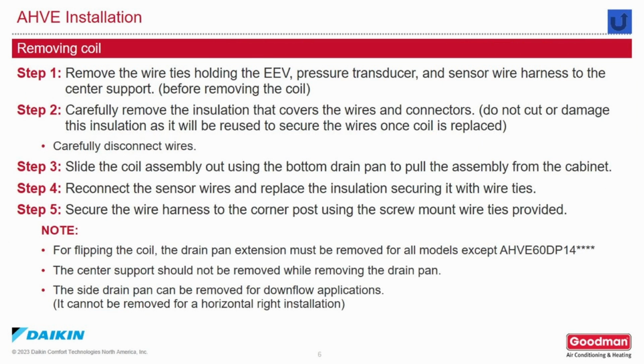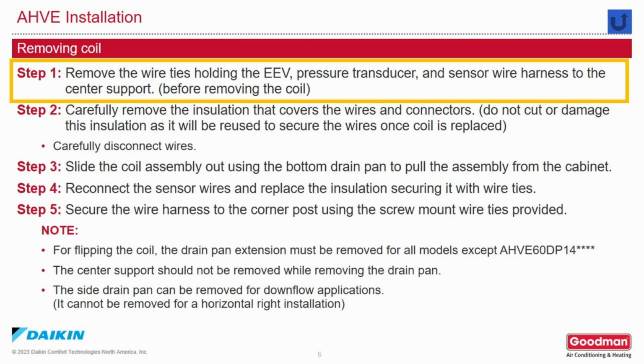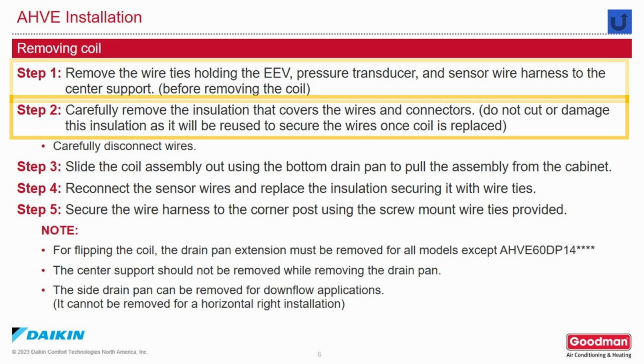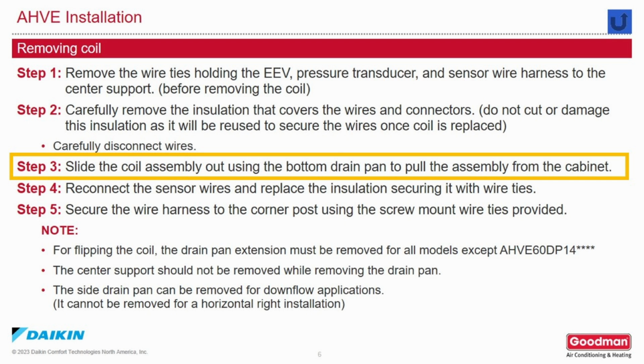To remove the coil, first remove the wire ties holding the EEV, pressure transducer, and sensor wire harness to the center support before removing the coil. Next, carefully remove the insulation that covers the wires and connectors. Do not cut or damage this insulation because it will be reused to secure the wires once the coil is replaced. Carefully disconnect the wires.